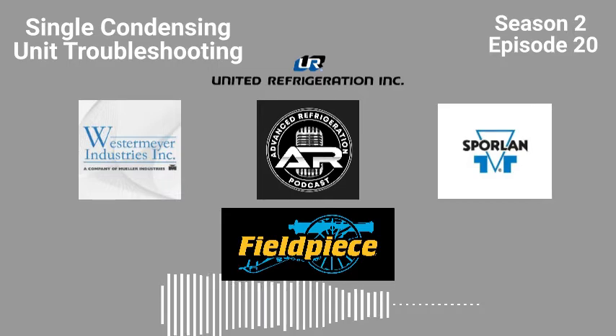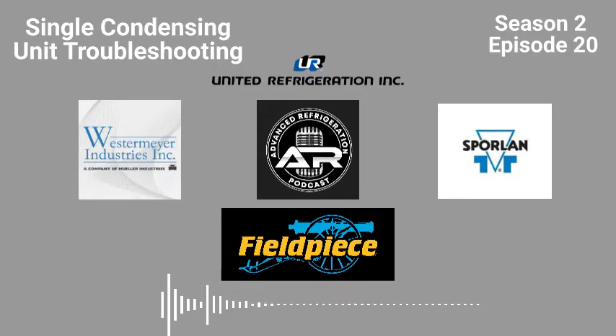See, the only other option that I have is to basically put in a bigger port. You know what I mean? Because by putting in a bigger port, the pulse valve is going to shut down anyway. It's going to cycle the way it is. So I've never seen a pulse valve oversized. I guess if it would open up for 2 seconds and then flood the coil, but that thing would have to be huge on top of the fact you have the distributor nozzle.